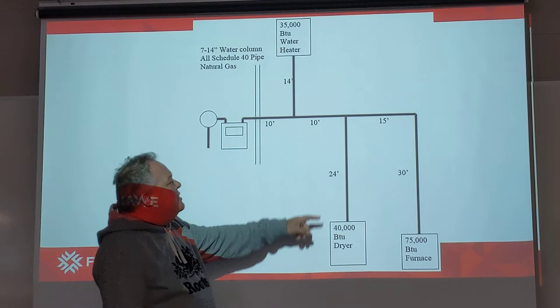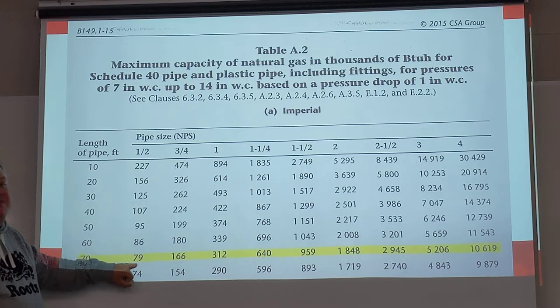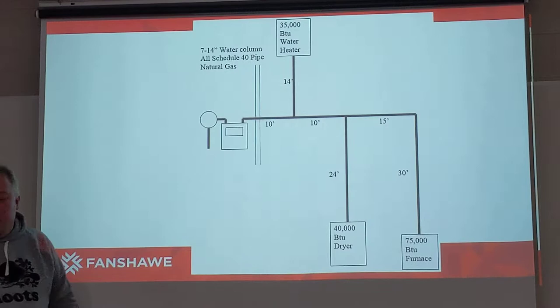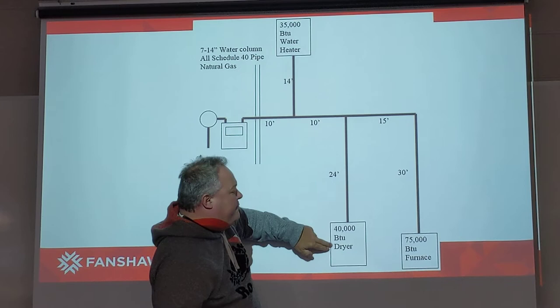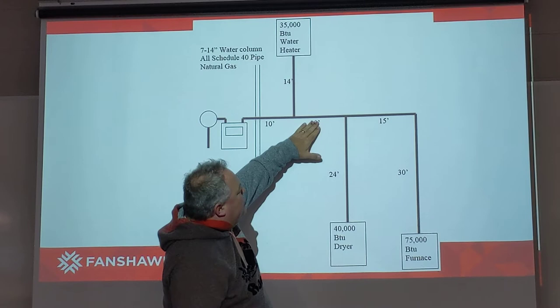The next thing we're going to do is size the line down to the 40,000 BTU gas dryer. Same type of application — we're still going to use the 70-foot code zone. Because the BTU load to that appliance is only 40,000 BTU, that line will be half-inch as well. With a capacity of 79,000, a half-inch line appropriately serves that 40,000 BTU dryer. So we've got half-inch coming up here, half-inch across, and half-inch coming up to the dryer. Now this 10-footer has to serve both the 40,000 and 75,000 BTU equipment.